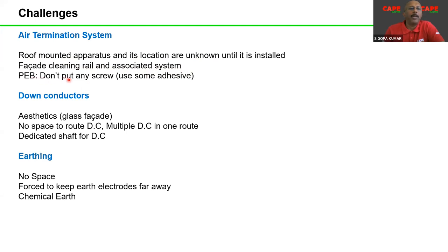Then in PEB buildings, one of the biggest challenges which we always face is the usage of screws. Don't use any screw. Don't put any hole. Use some kind of sticking material, adhesive material. So with an adhesive, you connect your conductor holders onto the RCC. Please understand that these adhesives have a certain life, probably 5 years or 7 years. After 7 years, you have to replace it. And more than that, by using adhesive, you are isolating the lightning protection. And in case of any strike, there will be a spark over across the adhesive tape.